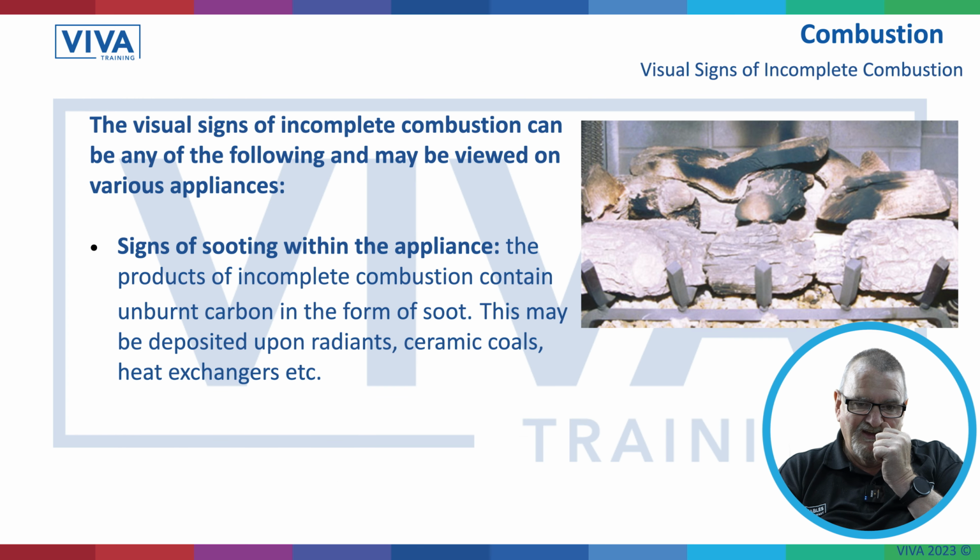It's an absolute danger. But not all appliances that are burning incompletely and incorrectly are that noticeable. Some of them look quite okay. It's when you start getting in and inspecting and checking them. And then things like these, what we call live fuel effect fires, gas fires that are designed to look like a coal fire. They've got coals or log effects on there where the flame passes through to give the illusion of a true open fire.